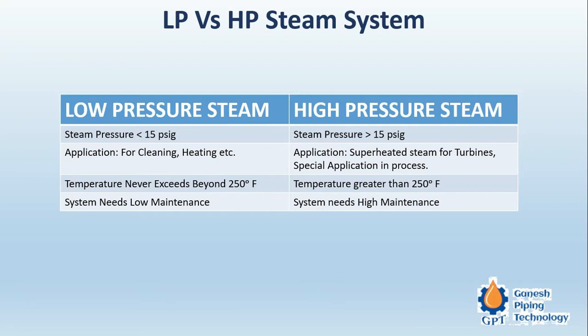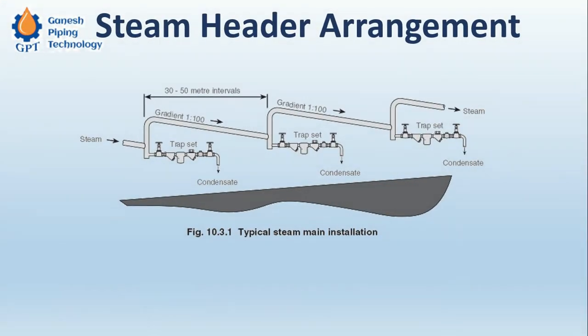For low pressure steam, temperature never exceeds 250 degrees Fahrenheit. For high pressure steam it is greater than 250 degrees Fahrenheit. Since the pressure and temperature are not that high, low pressure systems need lower maintenance, while high pressure systems require more maintenance.